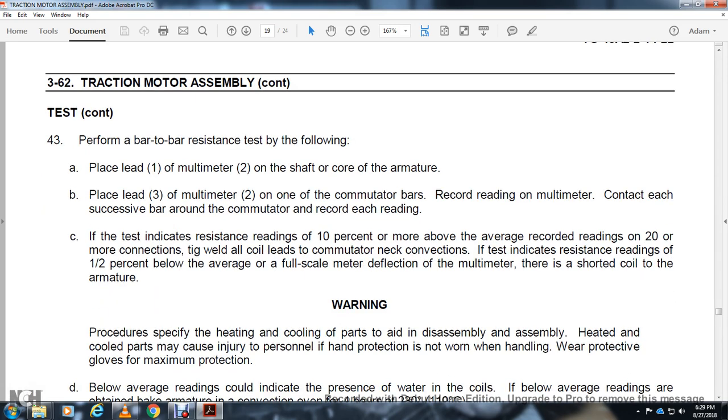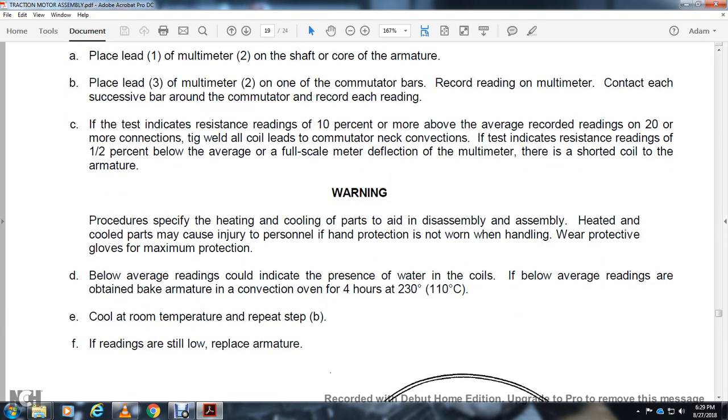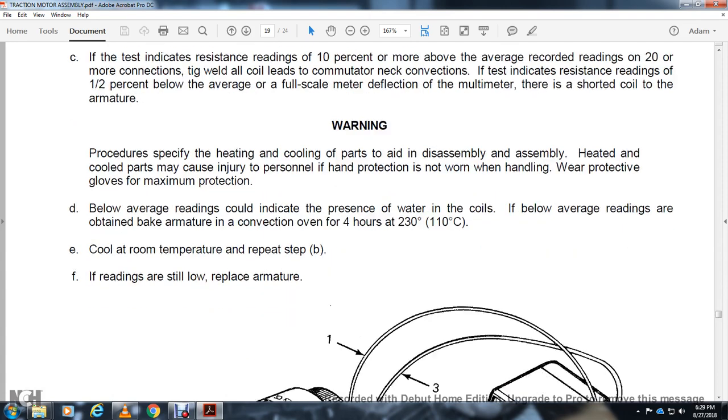Warning — heated or cooled parts during disassembly may cause injury to personnel. Hand protection must be worn; wear protective gloves for maximum protection. Below-average readings could indicate the presence of water in the coils. If below average readings are obtained, bake the armature in a convection oven for 4 hours at 230 degrees Fahrenheit. Cool to room temperature and repeat step B. If readings are still low, replace the armature.